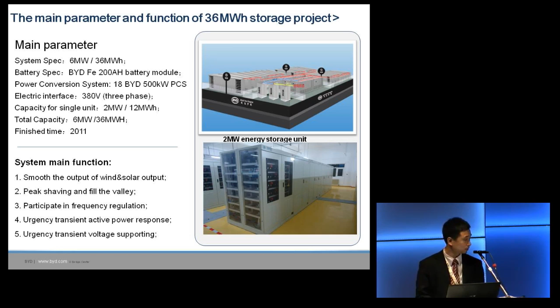So the topology of the whole system: the battery, we have around 68,000 pieces of the 200 ampere hour battery system here, each with a battery management system to support it, going through the 500 kW PCS through the transformer to supply the grid.